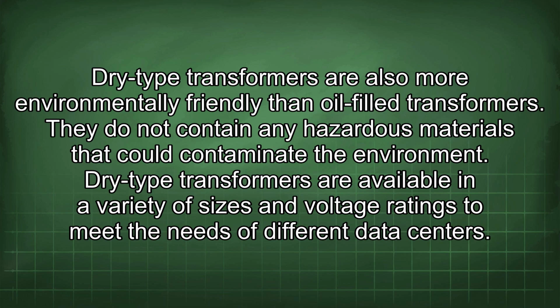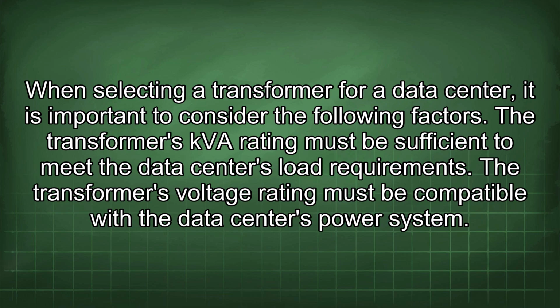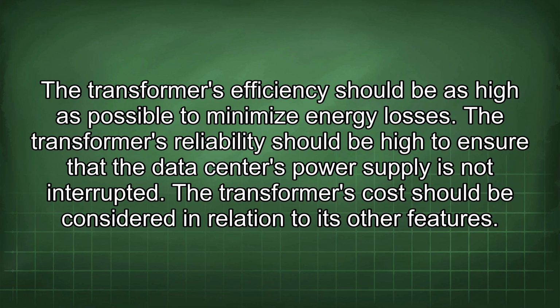Dry-type transformers are available in a variety of sizes and voltage ratings to meet the needs of different data centers. When selecting a transformer for a data center, it is important to consider the following factors. The transformer's kVA rating must be sufficient to meet the data center's load requirement. The transformer's voltage rating must be compatible with the data center's power system. The transformer's efficiency should be as high as possible to minimize energy losses. The transformer's reliability should be high to ensure that the data center's power supply is not interrupted. The transformer's cost should be considered in relation to its other features.